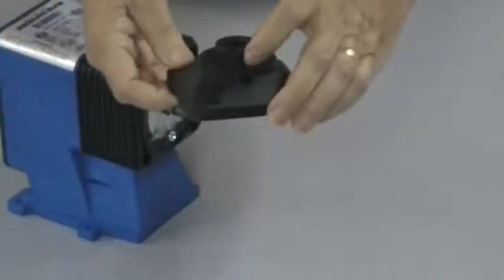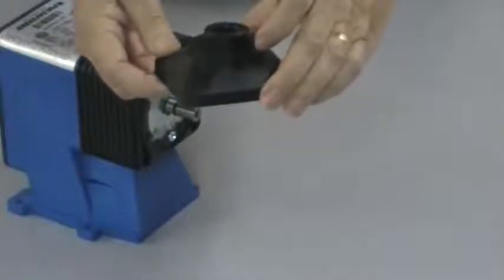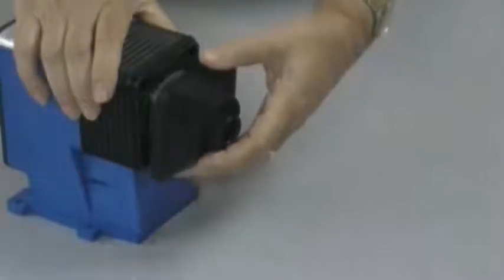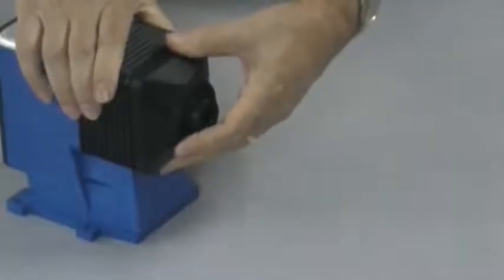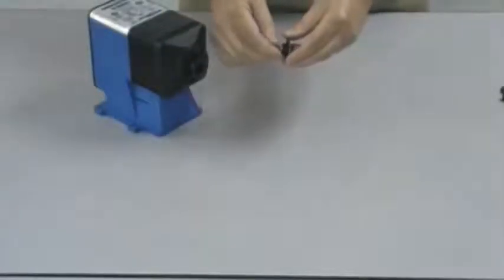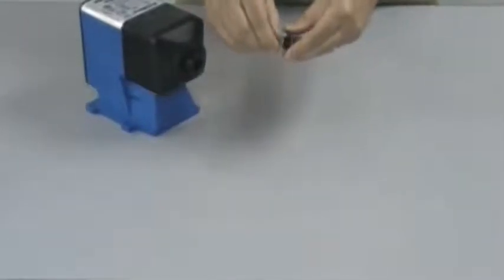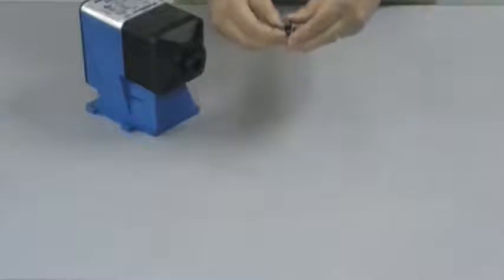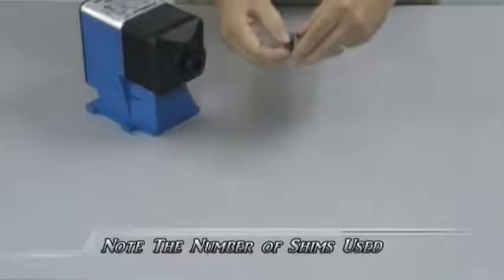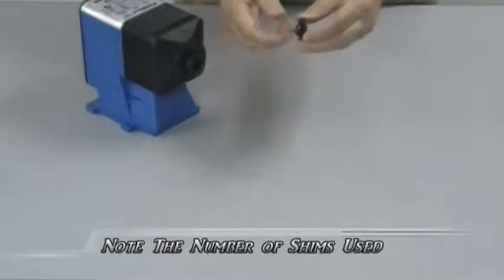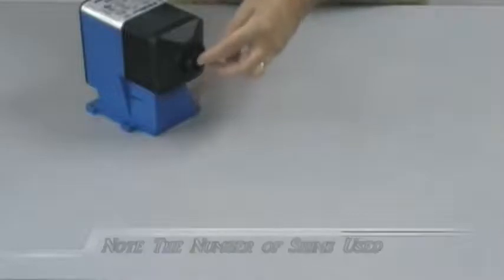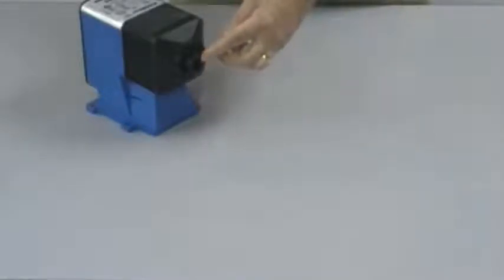The adapter has a weep hole at the bottom of one of the sides of the adapter. That weep hole goes down, so the adapter is placed over the shaft with the weep hole down. Before installing the new diaphragm, look at your old diaphragm and discover how many shims are in place on the old diaphragm. This old diaphragm had 2 shims on it. Keep in mind there could be a shim stuck to the end of the shaft.